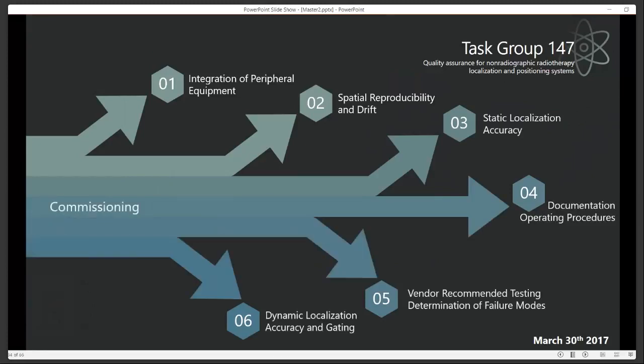Again, it gives you a number of different tests. The integration of peripheral equipment is, again, notice an overlap with the acceptance testing. Spatial reproducibility and drift, and dynamic localization, accuracy and gating, and static localization and accuracy. All things that you need to be checking. Any vendor recommended testing that they put in there related to their implementation of algorithms is very, very important, but is not the only sole thing you need to do.